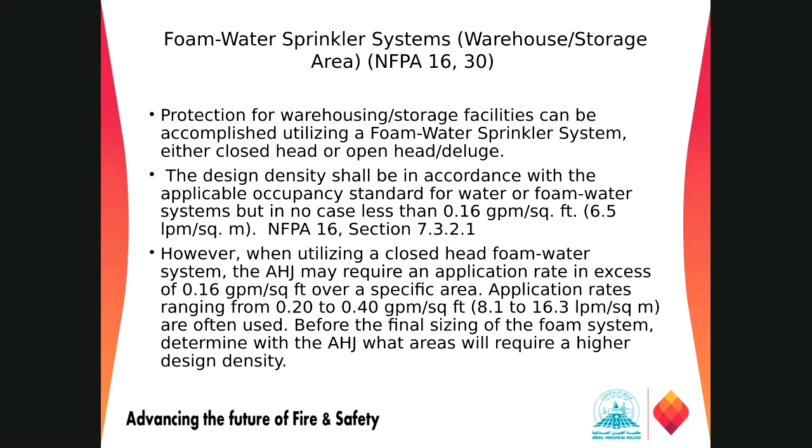So now we are talking about the foam water sprinkler system for warehouse storage protection, right? Foam and water mixed together and coming as a solution for fighting the fire. Protection for warehouse storage facilities can be accomplished utilizing a foam water sprinkler system. It might be a closed one, or it might be the open head, which is the deluge one, right? And the minimum density should be 0.16 GPM per square feet as per NFPA 16 7321, right?